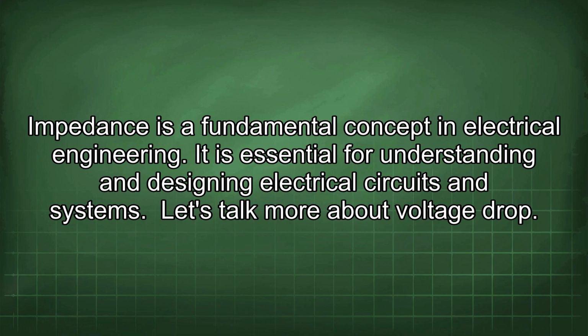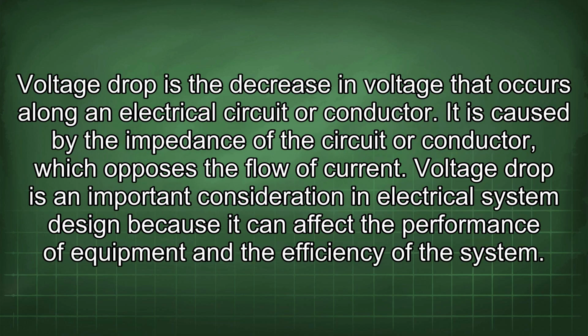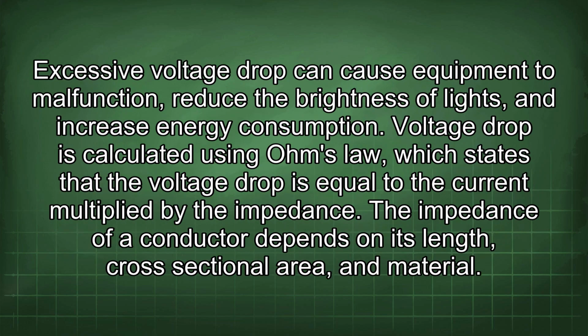Let's talk more about voltage drop. Voltage drop is the decrease in voltage that occurs along an electrical circuit or conductor. It is caused by the impedance of the circuit or conductor, which opposes the flow of current. Voltage drop is an important consideration in electrical system design because it can affect the performance of equipment and the efficiency of the system. Excessive voltage drop can cause equipment to malfunction, reduce the brightness of lights, and increase energy consumption.